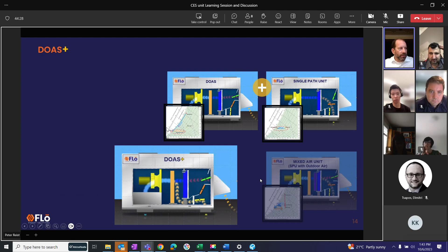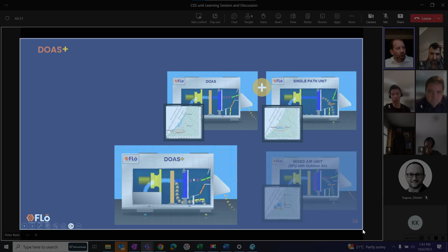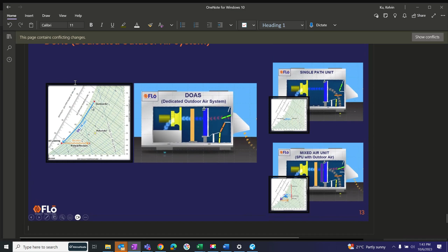That's actually what it's doing. And so this is where we came up with something called DOAS Plus. This is still the same concept of DOAS. The outside air is going over the coil. And if I look at the psychrometric, it's the same curve here. We're dehumidifying the outside air. But now what we're doing is we're bringing the return air around the coil. We call it a bypass, and we mix it after the coil.